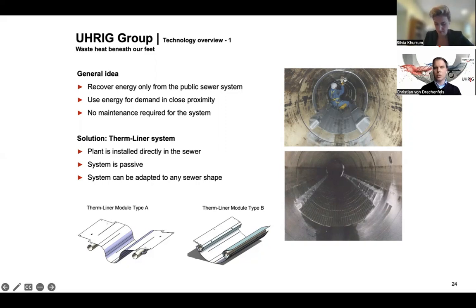That's our solution. We install these modules directly in the sewer, and we always say this system is a passive system. As I said, it's just a stainless steel heat exchanger that we are producing. We are designing it, producing it, and installing it ourselves usually, and it's always tailor-made. It is adapted to the sewer shape and of course to the specific project and the energy demand. You can see on the bottom that we've got basically two different types of modules we can use, type A and type B. When there is a specific project, we will decide what's best for it. Next slide, please.